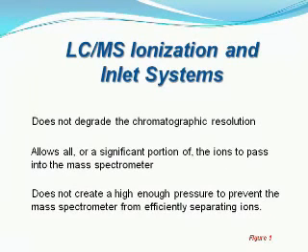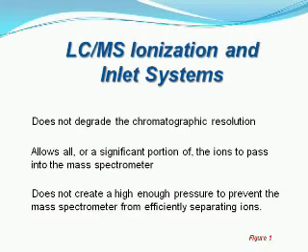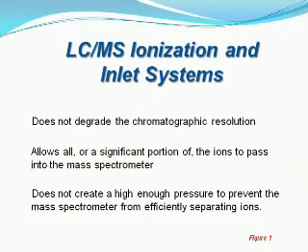The third requirement is that the ionization and inlet systems do not create a high enough pressure to prevent the mass spectrometer from efficiently separating ions. In simpler terms, we simply cannot allow all of that vapor produced by the HPLC mobile phase to pass into the mass spectrometer, because we would no longer have a vacuum in the mass spec, and therefore we'd no longer have a mass spec — we'd no longer be able to do mass analysis on the injected ions.